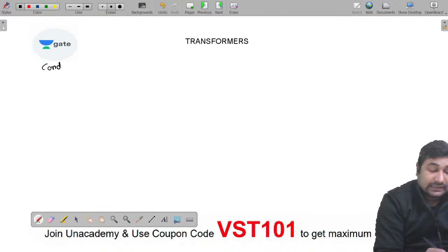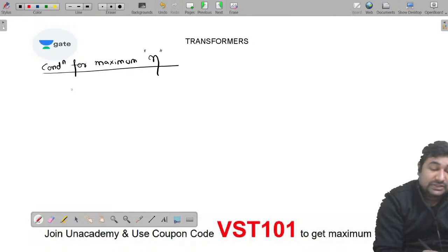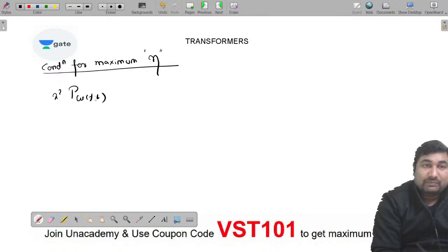Condition for maximum efficiency, this is the 10th point, efficiency part. You have to remember that the operating copper loss, x square PCUFL where PCUFL is full load copper loss, equals iron loss. These are the conditions at which efficiency is maximum.